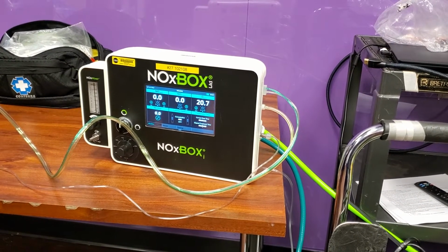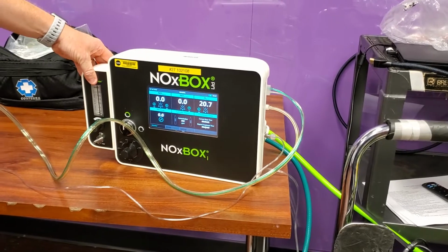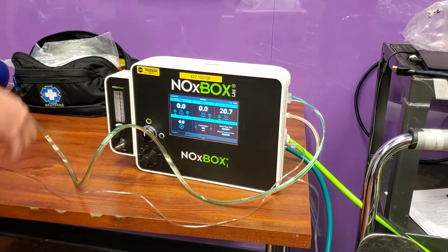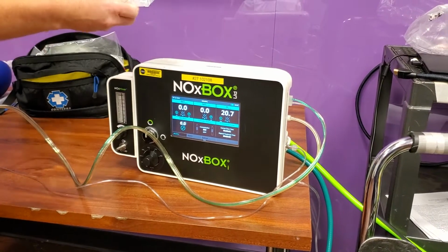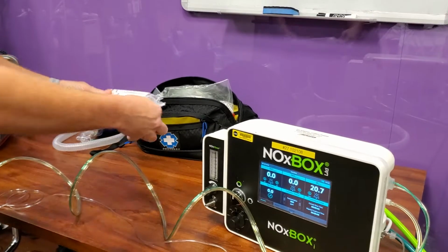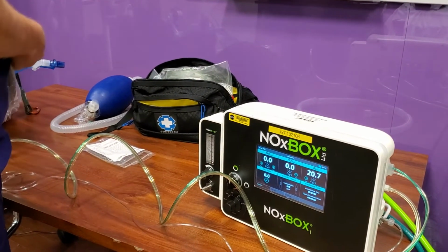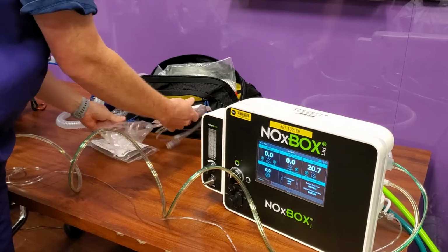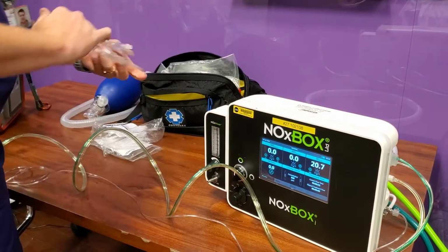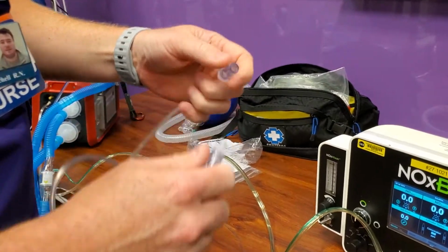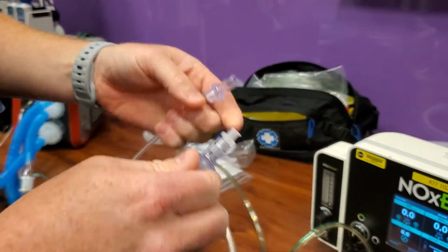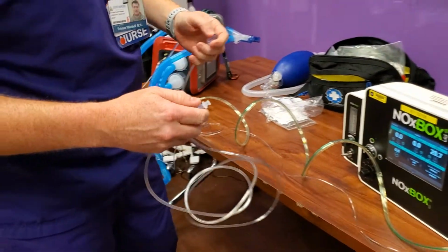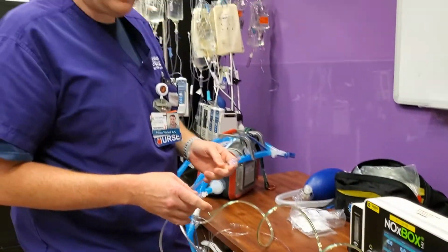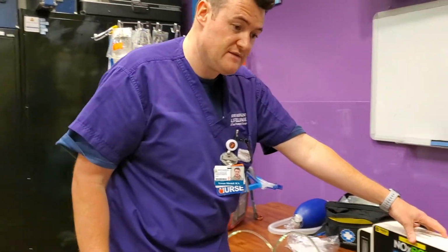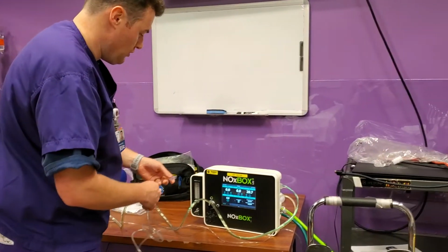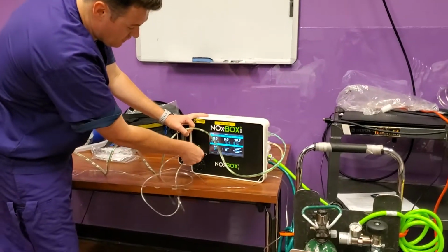If there was an emergency of any kind, obviously, as I mentioned, we'd have to go onto our backup mixer here. So what we do here, as I mentioned, is we have our tubing in the front that we're going to use. And this piece here comes preset, and we have a regular oxygen tubing end on one end and then our luer lock on the other end. And this would be in the case that, not when we're bagging the patient, but if our ventilator is working perfectly fine and it's just that this module has failed, but we can still use the ventilator. What we're going to do here is switch it into our backup delivery mode.